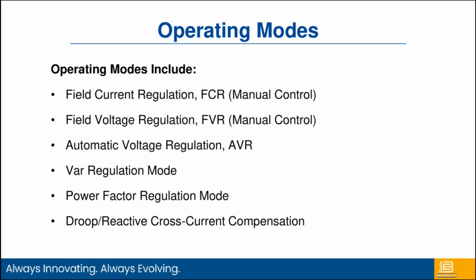The same scenario is true for power factor regulation. I do not want to be able to change voltage with this particular machine. I just want to be able to change the VAR component out of that machine to change the phase angle between the reactive power and the real power. And that phase angle is ultimately power factor. So I can do power factor correction at a plant level or at my point of common coupling.